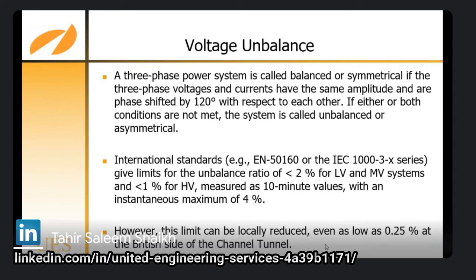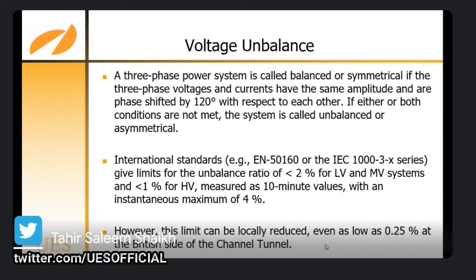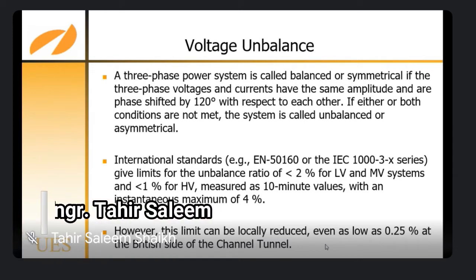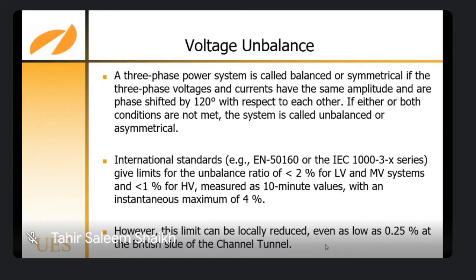International standards such as EN 50160 or the IEC 61000-3-x series give limits for the unbalance ratio of less than 2% for LV and MV systems and less than 1% for HV, measured as a 10-minute value with an instantaneous maximum of 4%. However, this limit can be locally reduced even as low as 0.25% on the British side of the channel.